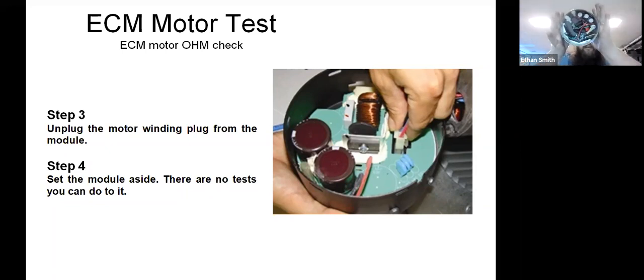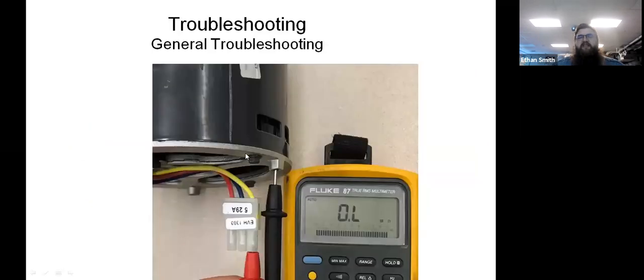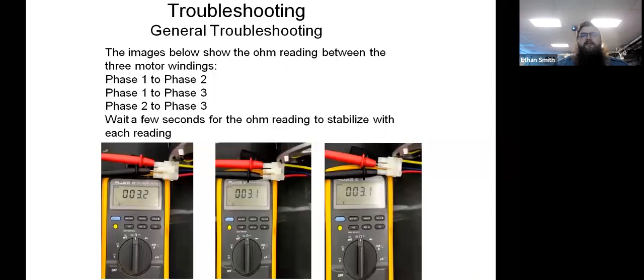Here's a picture. Here's one of the newer ones that you'll see out there. They all basically have a harness that goes between that module and the motor itself. You can see he's unplugging that one badly right there. We can't really test the module, but we can do some ohm checks on the motor to see if the windings are intact. So here's one with a plug on it. He's just got one meter lead in there, and he's going to check to ground between all of those leads. You should have an open line to ground on all leads of these variable speed motors.